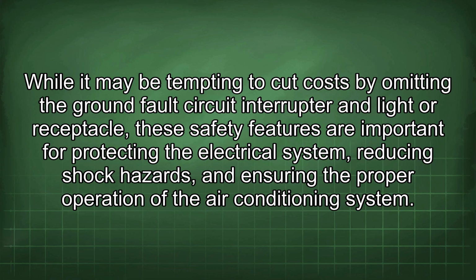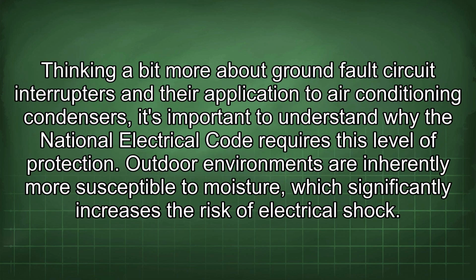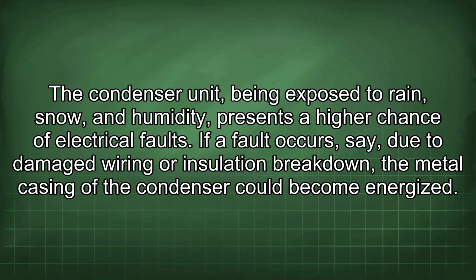Thinking a bit more about ground fault circuit interrupters and their application to air conditioning condensers, it's important to understand why the National Electrical Code requires this level of protection. Outdoor environments are inherently more susceptible to moisture, which significantly increases the risk of electrical shock. The condenser unit, being exposed to rain, snow, and humidity, presents a higher chance of electrical faults.